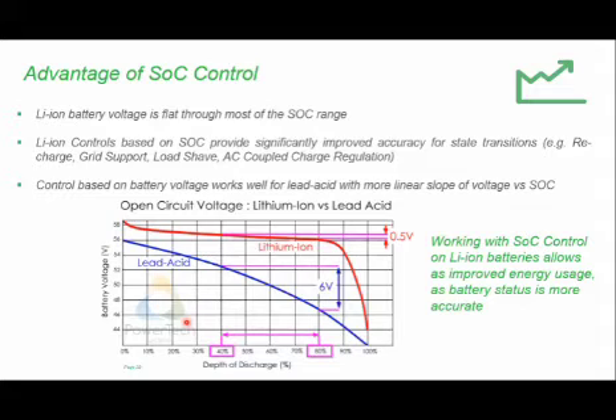Let's say you have a 48-volt battery system. When the battery is charging, it can go as high as 57 volts. When it's low, it can go as low as 44 volts. So you have a pretty steep slope in terms of voltage. For example, at 80% full versus 40%, you can see there's a 6 volt variation.